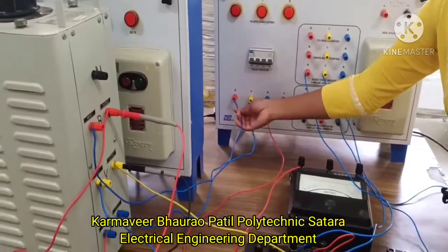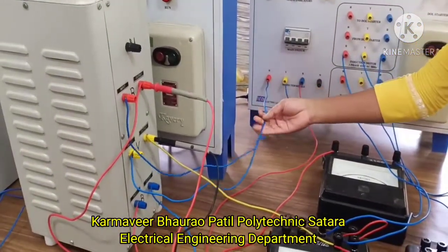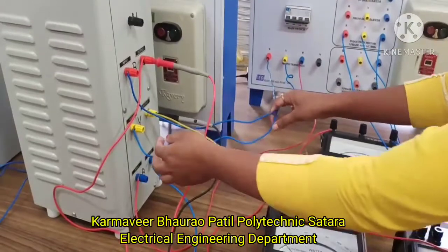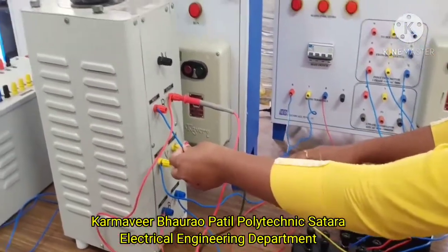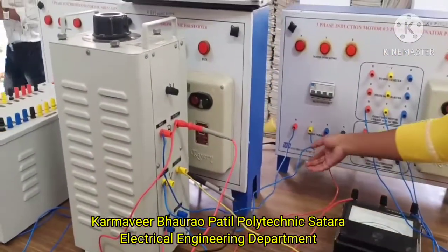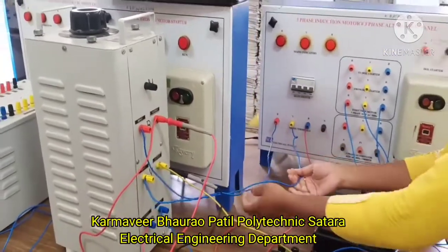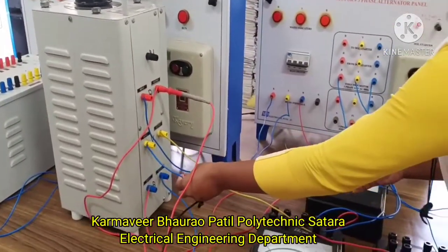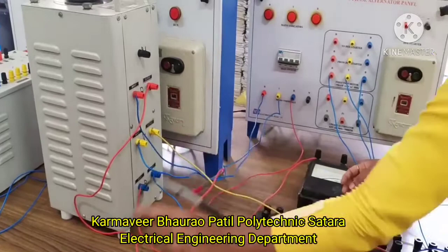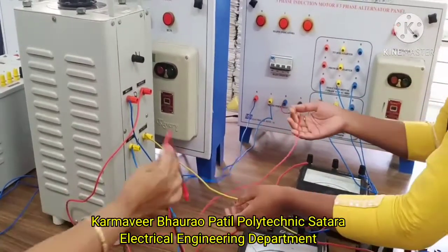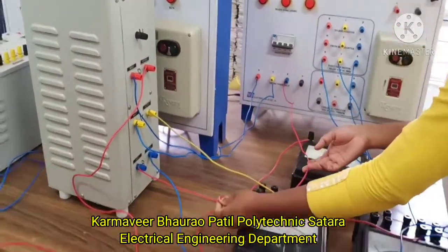So first, the connection comes from the R phase of the main terminal to the R phase input of the auto transformer. Next, the Y phase similarly comes to the Y phase of the auto transformer's input. Same with the B phase, which will come to the auto transformer's B phase.